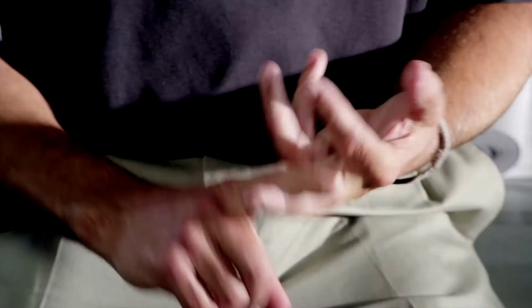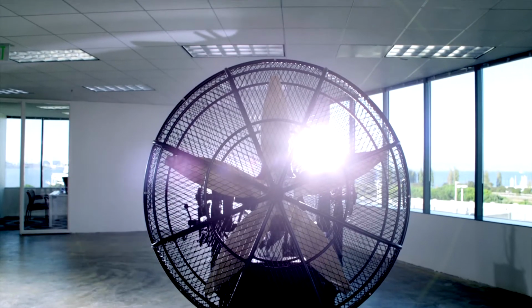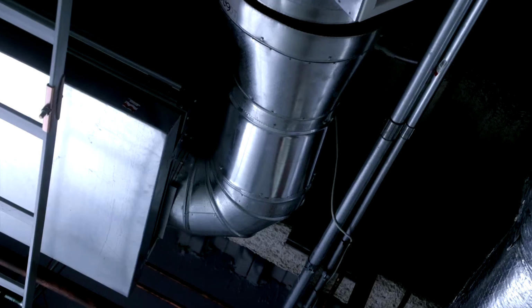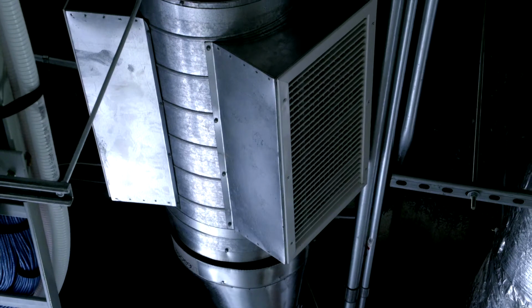We came in and found all the thermostats were incorrectly set. I go up to the rooftop and 80% of the economizers aren't hooked up correctly. The indoor blower, coils, the heat exchanger, the belts, the compressor, the fans, if all those things are dirty, the system could be fighting itself, using a lot more electricity or natural gas than it really needs to.